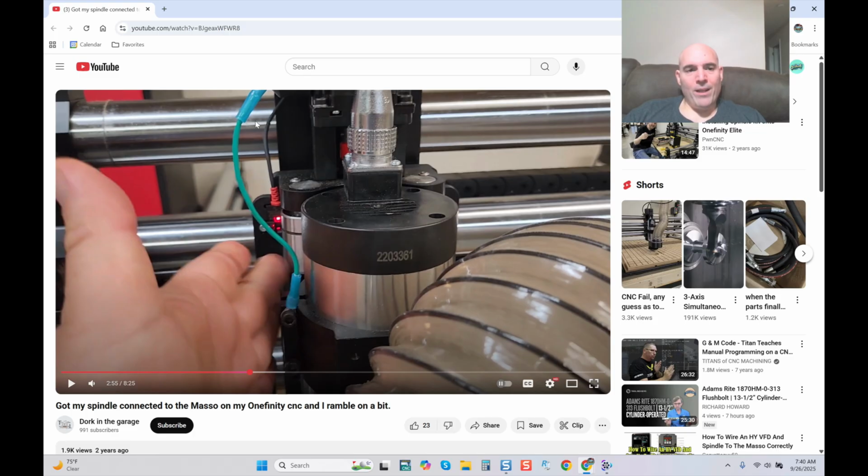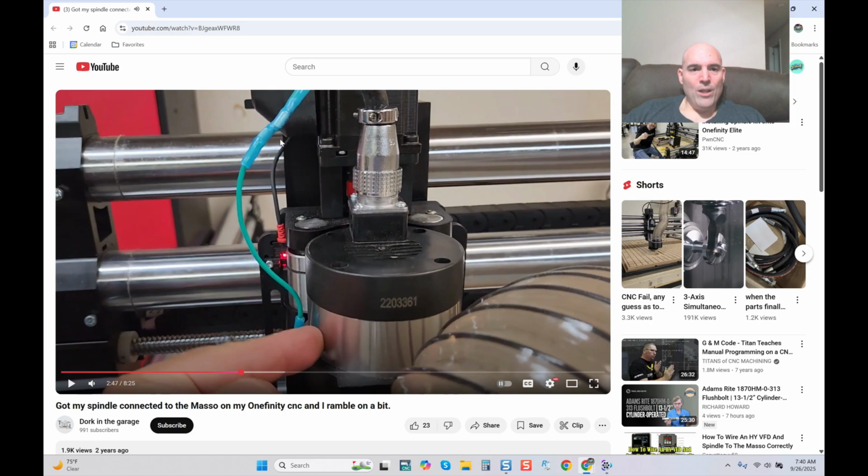The other thing I want to draw your attention to is whenever you guys are doing a lead, I don't know why these guys are all, they're using splices. We don't use splices. You should have one direct lead as a ground. Splices have problems. The more connectors you have in a loop like that, you're adding more resistance. And on top of that, you're adding more potential for problems. And that's something that you have to take into account. All of this should have been one lead. And then this should have came over here with a ring connector. And that's why I prefer soldering. Soldering done properly with flux and the proper technique assures this cable lasts forever.